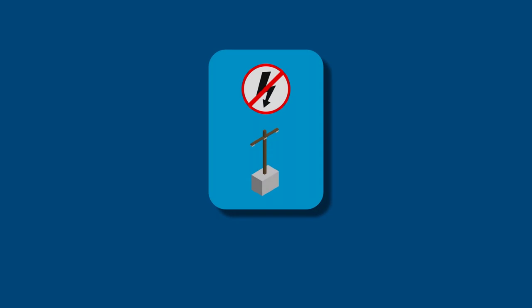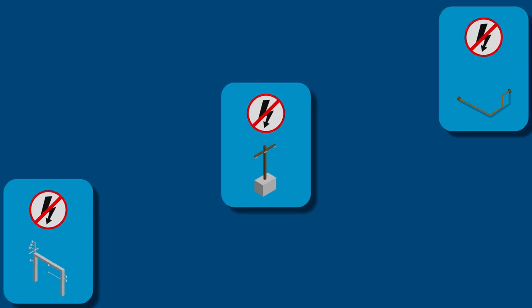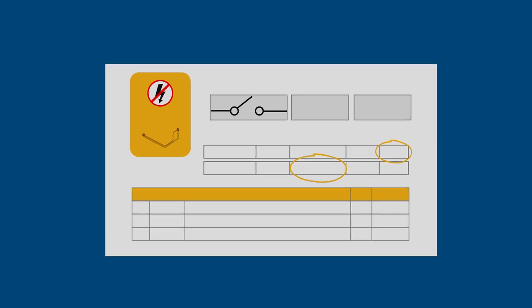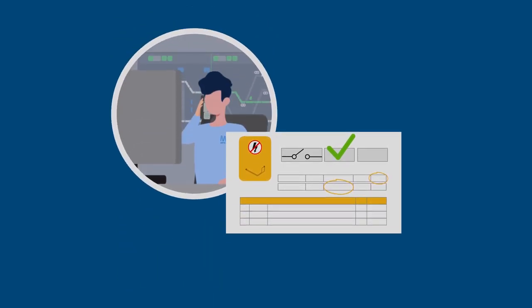A request application for switching or isolations of an electrical asset must be submitted at least 10 days prior to works being undertaken. MTM's high voltage switching planners assess each access authority request and prepare a switching schedule detailing the isolations and earthing or short-circuiting required to provide safe access to the apparatus. The switching schedule is then checked by an independent high voltage switching planner or high voltage electrical operator with appropriate system competency and submitted to the Electrical Control Centre.